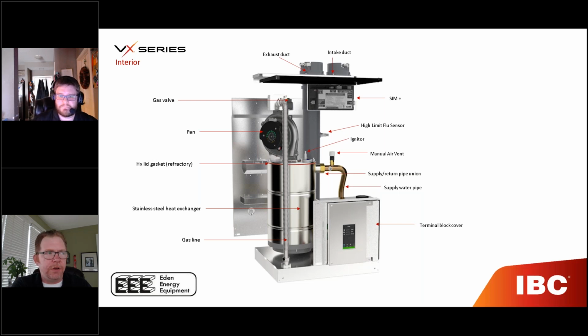This is the V10 control. This is the terminal block cover. No surprises under the box for those of you who are used to the V10 control. You have your line voltage connections for your pumps and/or zone valves, depending on how you're wiring it, and then you have your thermostat hookups as well as your interlocks, your outdoor reset, etc.